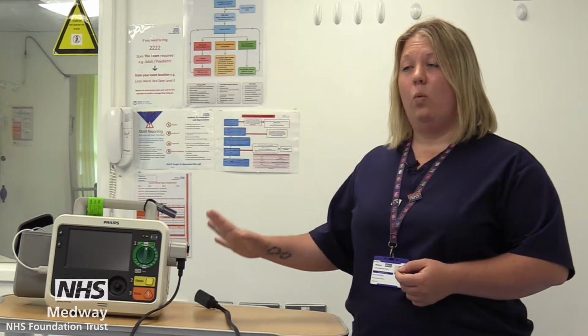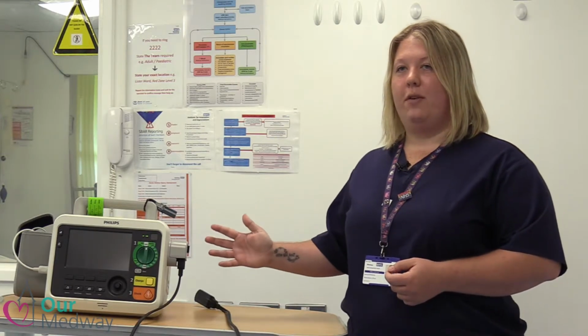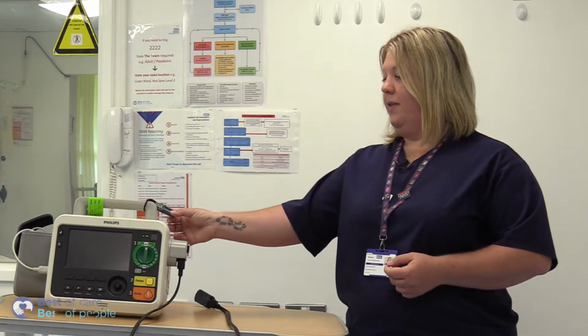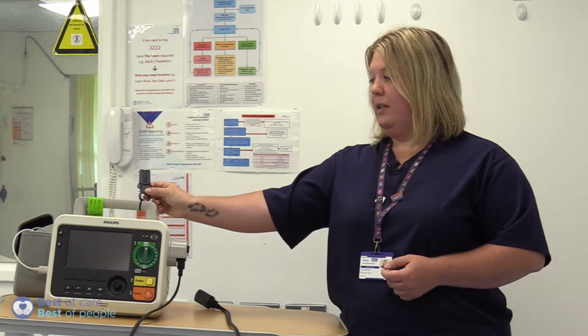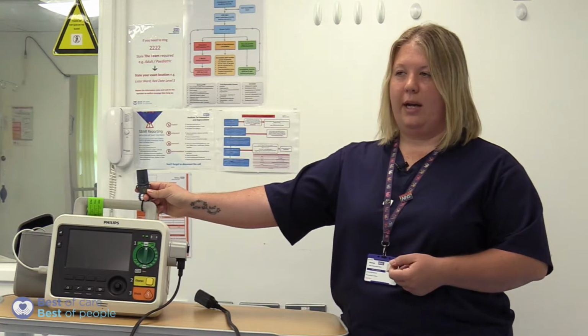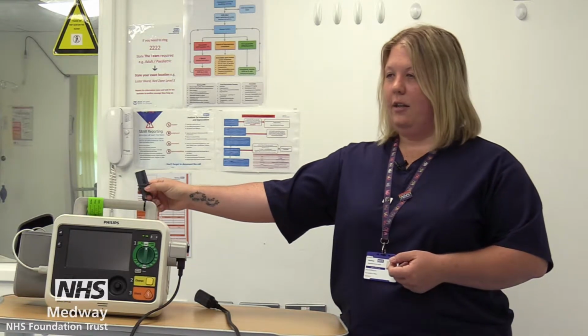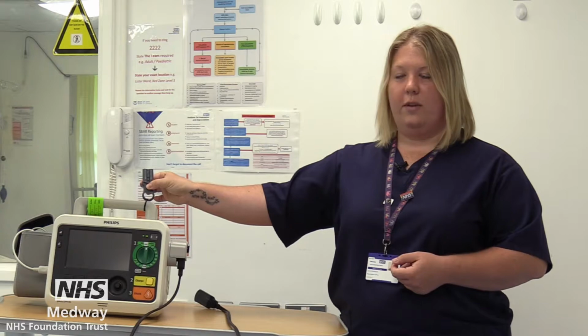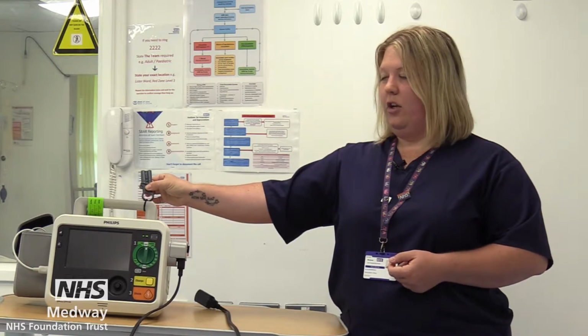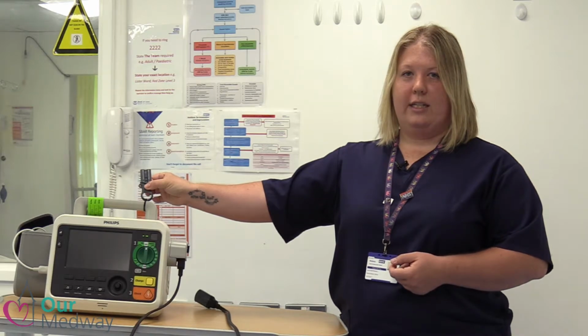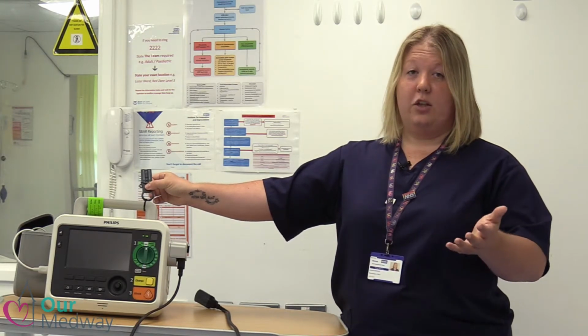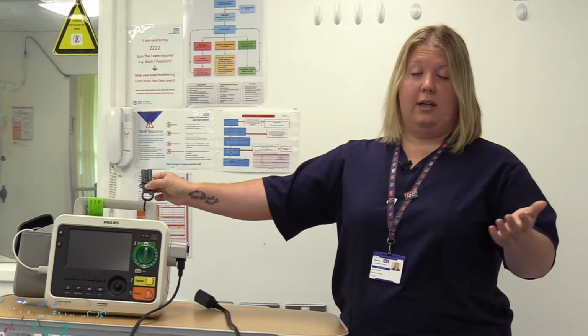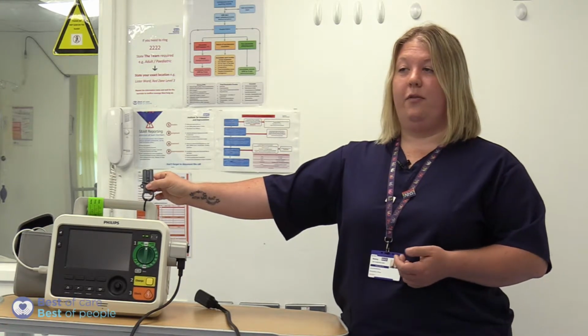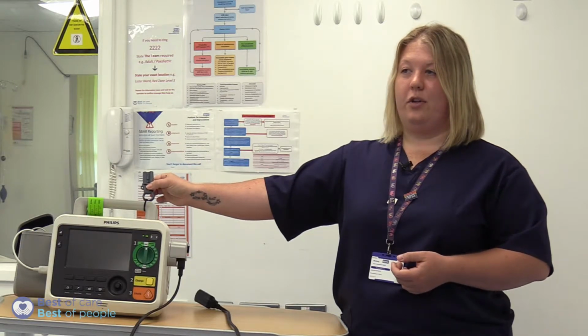This needs to be checked once a day and once per month. So the daily check I'm going to show you first, and then the monthly operational check I'll show you second. So to start the test, one of the first things we need to do is make sure that our defibrillator cable, the cable that we will plug our pads into, is attached to the test plug. These are cable tied to the top of all of these model of defibs. If for any reason you do not have one of these on your defibrillator, then you need to contact equipment services to get that rectified, because like I say, without this you cannot test your defibrillator, and if we cannot test it, we cannot ensure that it is safe for use on patients.